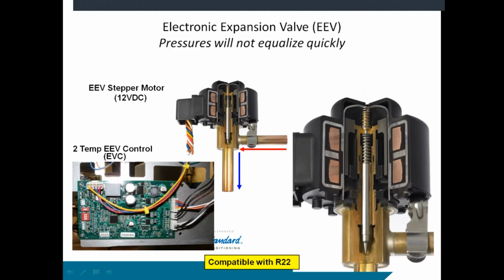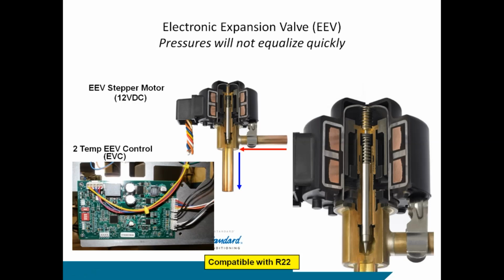Again, stepper motors are usually 12 volts DC. And also, when you shut the compressor off, a lot of times they'll go to a minimum position and the pressures won't equalize, at least not very quickly. So again, when you're doing compressor diagnostics, don't look for those pressures to equalize quickly. They may not, unless you've got a flow piston in there.